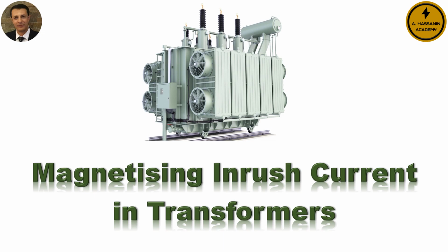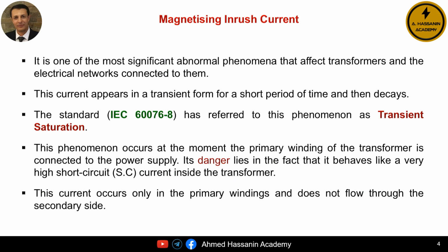Certainly, this current or inrush current can actually occur even when the transformer is in service. But how? We will find out together in this lecture. To begin with, we must understand that one of the most abnormal phenomena that power transformers are exposed to is the occurrence of magnetizing inrush current. This current is of course transient, random, and lasts for a very short period of time. For those who wish to study this topic in more depth, they can refer to the standard IEC 60076-8.